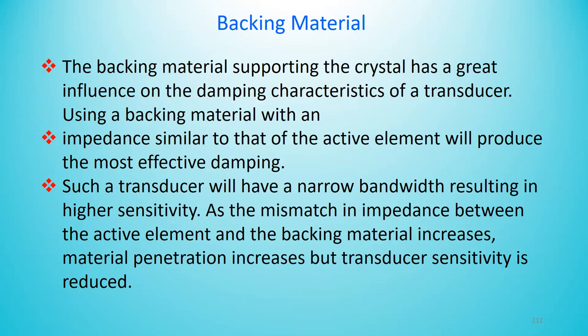The backing material supporting the crystal has a great influence on the damping characteristic of the transducer. Using a backing material with an impedance similar to that of the active element will produce the most effective damping. Such a transducer will have a narrow bandwidth, resulting in higher sensitivity.